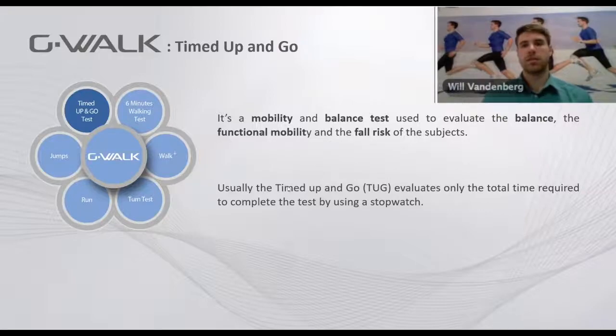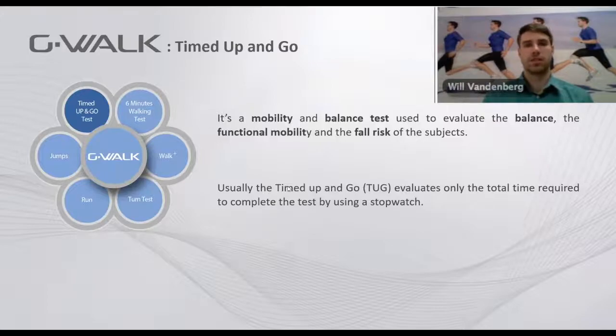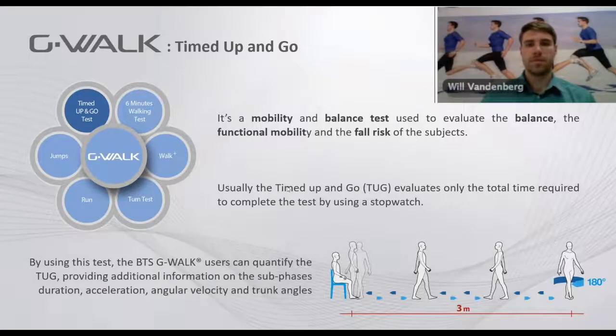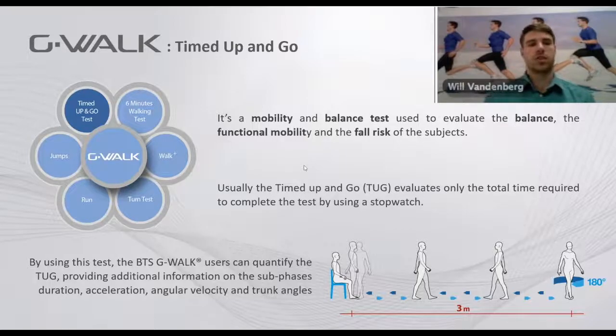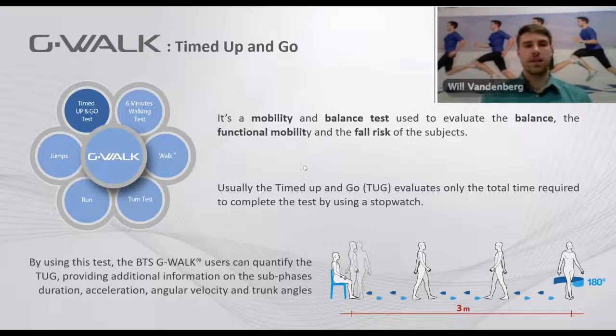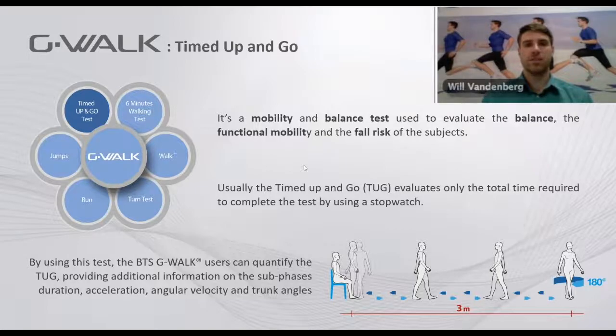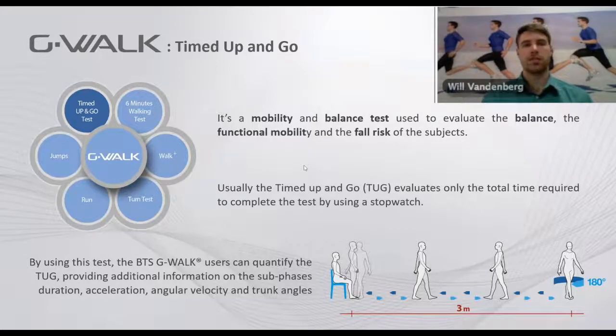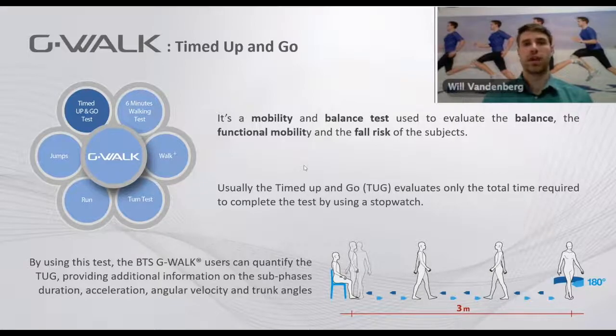Typically the test only evaluates the total time to complete the entire movement by using a stopwatch. But with the G-WALK, users can quantify this timed up and go test, providing additional information about each sub-phase, the duration of the sub-phases, as well as accelerations, angular velocities, and trunk angles throughout the test.